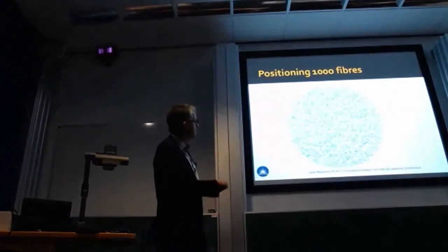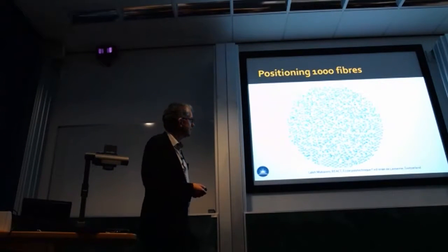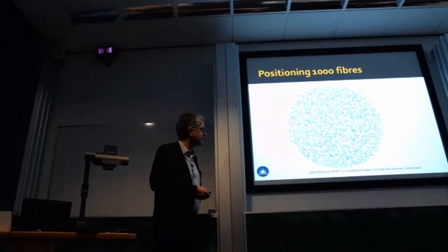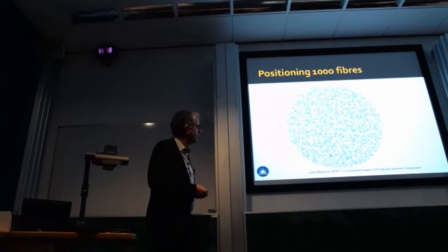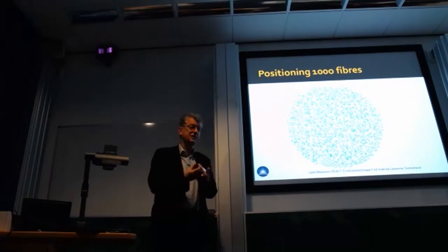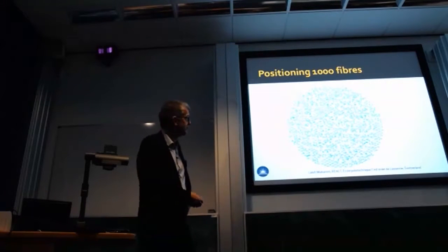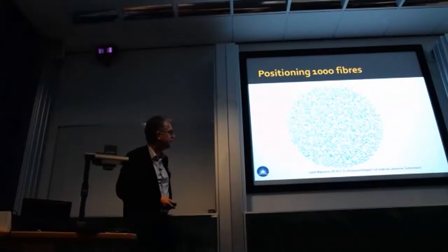Is that working? Oh, yes. So that's what it looks like when you've got 1,000 of these. So that's great. And if we could rely on the positioning using the stepper motors, we'd probably be very optimistic. So not only do we need some means to make sure that they don't collide, if they do collide, we need to be able to recover. We actually measure the electrical resistance, and if we get a short, we know they touch, so we can recover our position.